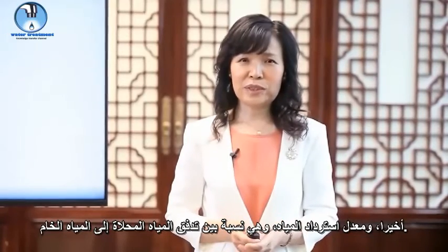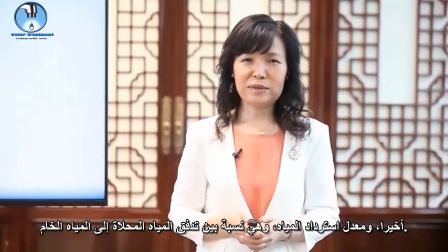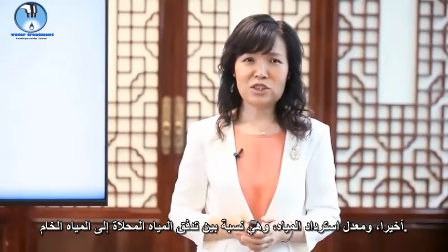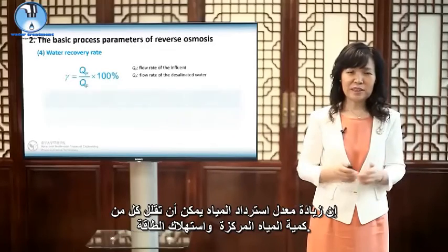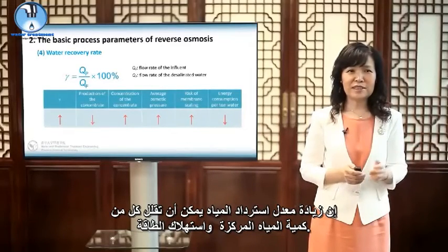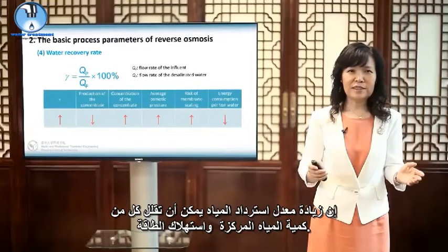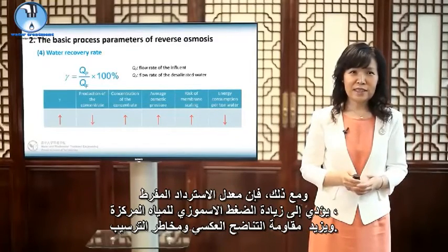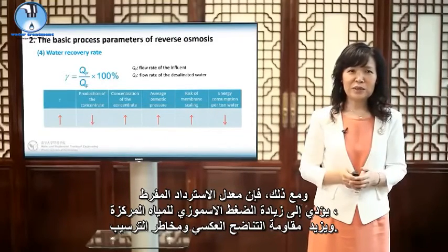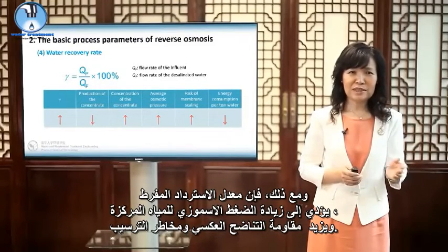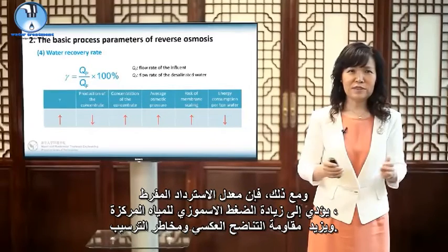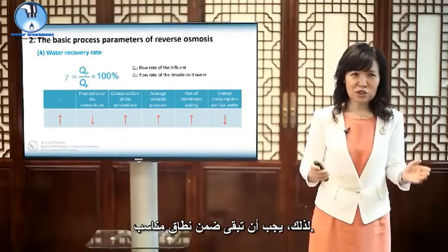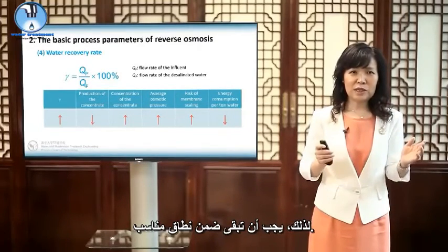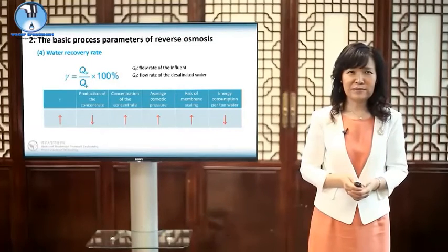Last, the water recovery rate, which is the ratio of flow rates of desalinated water to influent. The increase of water recovery rate can reduce both the concentrate amount and the energy consumption. However, excessive recovery rate would cause the increase of osmotic pressure of concentrate, increasing the reverse osmosis resistance and the scaling risks. Therefore, it should be kept within a proper range.